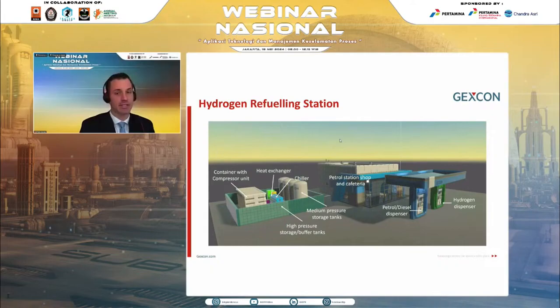For the system, the compressor for the refueling station was located in an enclosed space to the right of the module shown here. The main problem we faced is if there was a leak, there would be dispersion of flammable gas and a potential for a subsequent explosion.